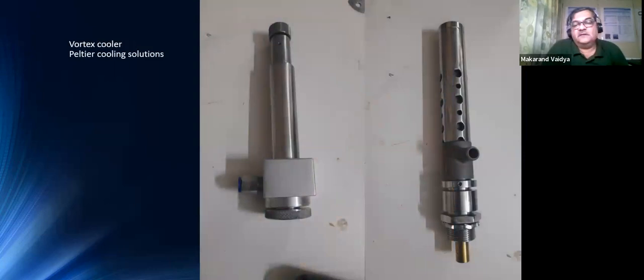Recently, along with all other friends from our family or tech forum, this is a classic example of synergy, working together. This is a product developed by our friend with me in collaboration, Mr. Sridhar Karkare. We developed this vortex cooler, which is very much required for purging and pressurizing systems. It's a pure mechanical refrigeration system, required to cool down any ambient temperature rise in the control panel, the purge control panel.